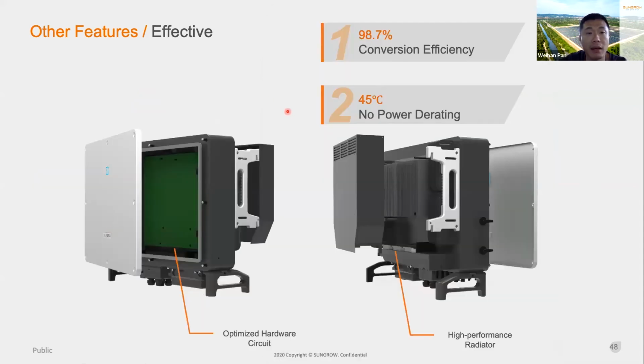And regarding the power conversion efficiency, the inverter is up to 98.7% without any derating, because we optimize the internal circulation, as well as put a high performance radiator at the back of the inverter. So the high efficiency is really important and guaranteed by Sungrow.